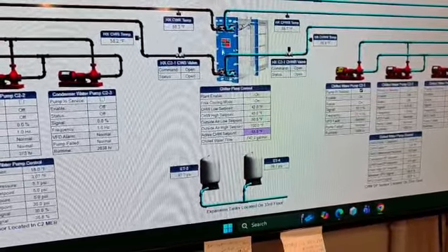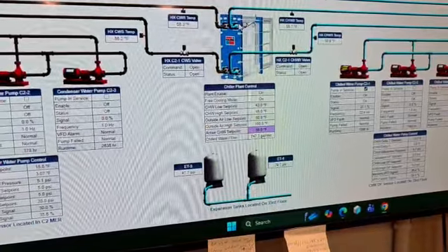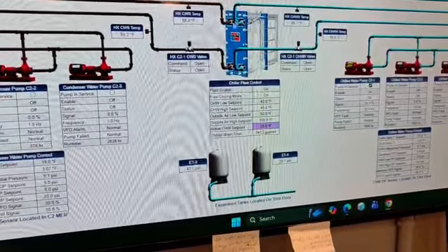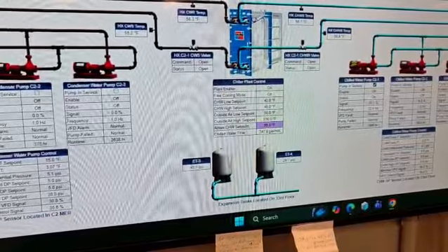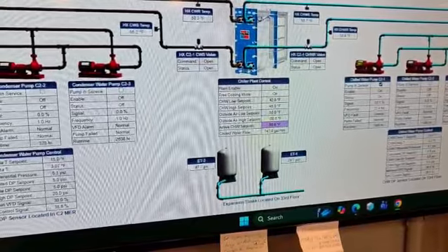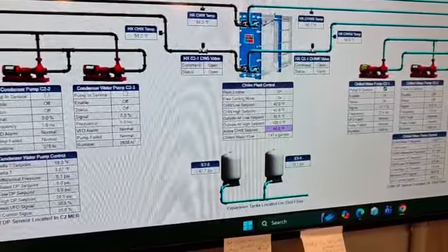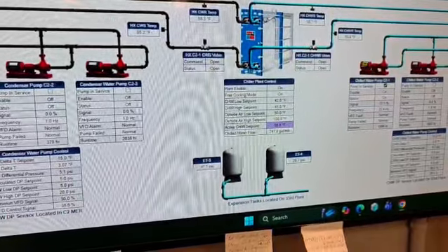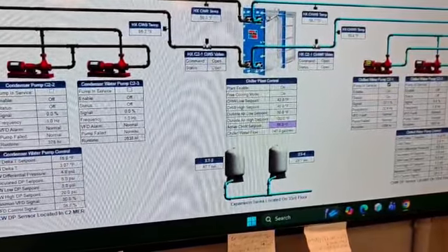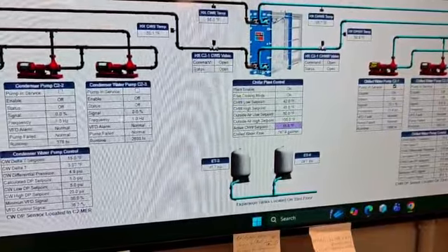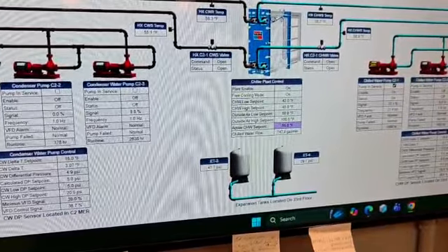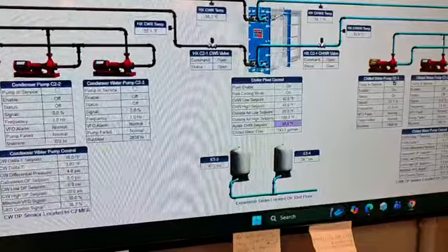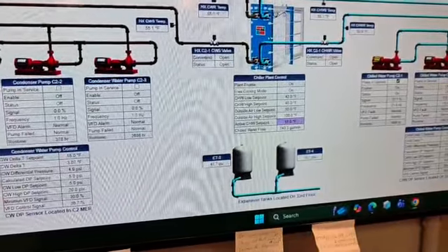So this is only on in between seasons. You're not going to see this running or open. You see the valves are open during summer because you need the water to be even colder, right? Because a lot of people are like, hey, I'm hot. So you need to generate a lot of cold, and the cooling tower by itself won't do it. But like I said, in between seasons, you could do this, which is called free cooling.